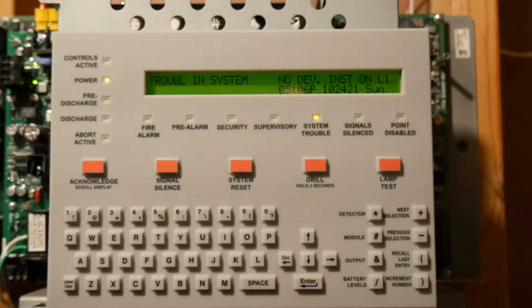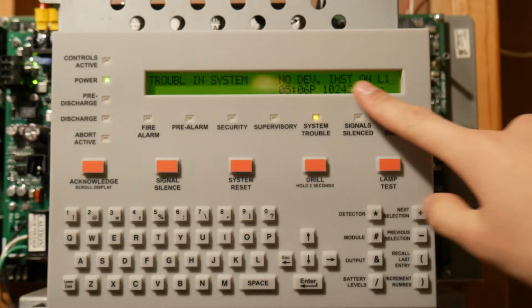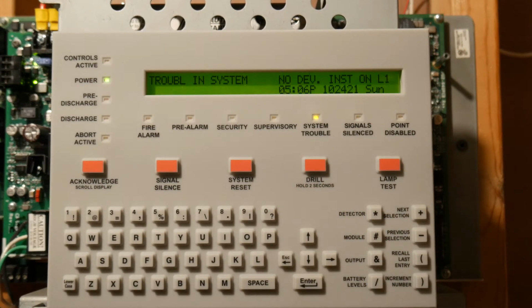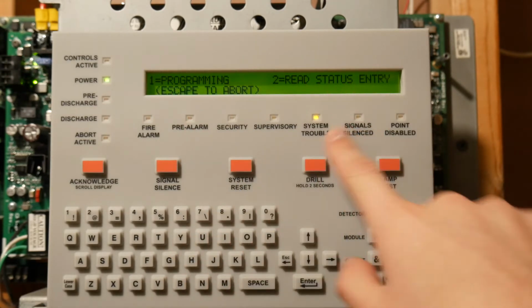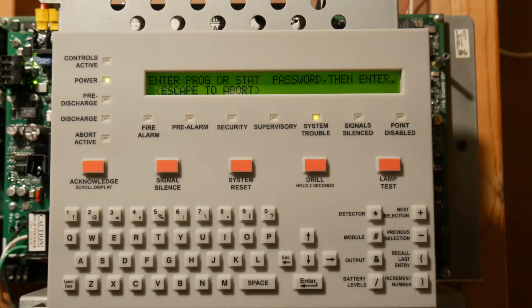So anyways, if you first power up the panel and install batteries and stuff, the only trouble you'll have is a no device installed on loop one. The reason you'll have this trouble is because even though you might have devices installed, you haven't programmed them into the system. So we need to program them in. We're going to press enter, and it's going to ask us, do you want to go into program mode or read status entry? We're going to press 1 for programming.